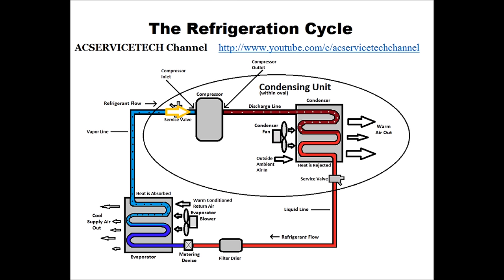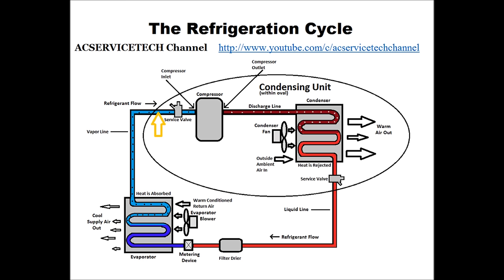You can check out some of my other videos on how to find the target superheat, because it's not on the rating plate like subcooling is. If you need to adjust the charge on a system with a piston or capillary tube, you'll have to set the superheat and make sure that you get it very close to the target superheat for efficiency and to make sure you don't have any liquid getting into the compressor on cooler, less humid days. Hope you enjoyed it, and we'll see you next time at the AC Service Tech Channel.